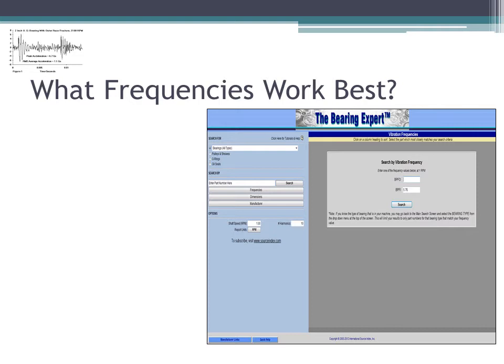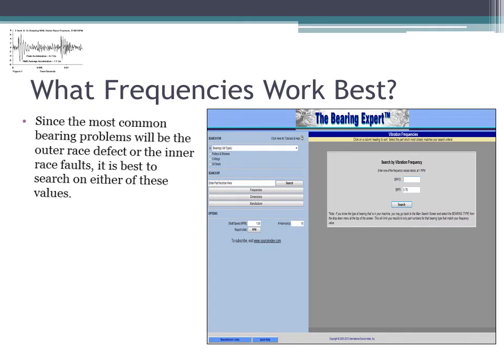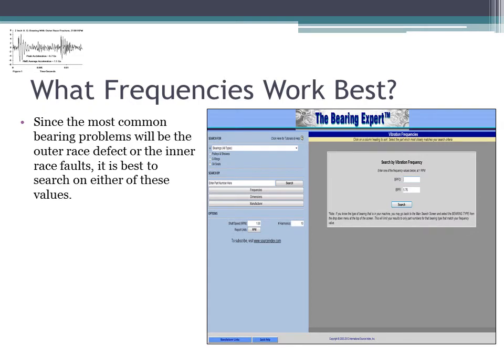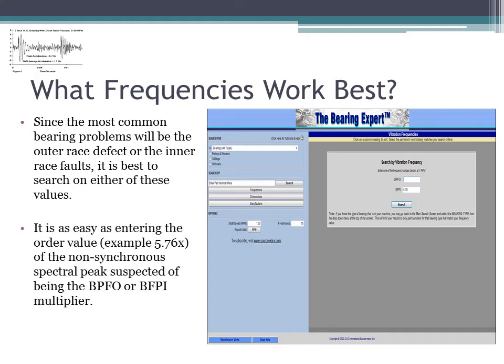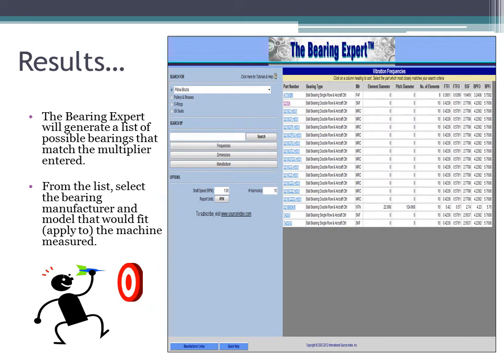You can select either one to enter your value. It's as easy as entering the order value — in this case we used 5.76 of the non-synchronous spectral peaks suspected of being the BPFO or the BPFI multiplier. The Bearing Expert will generate at the bottom a list of possible bearings that match the multiplier entered.